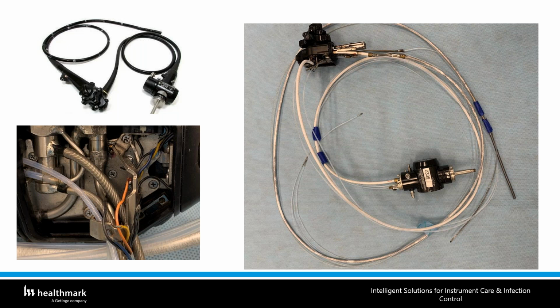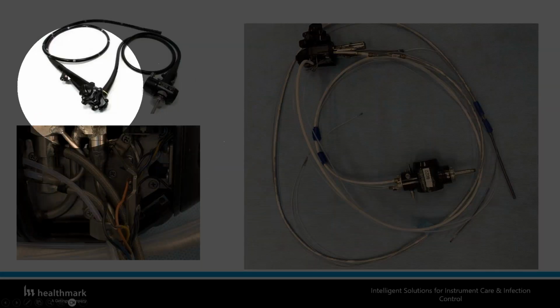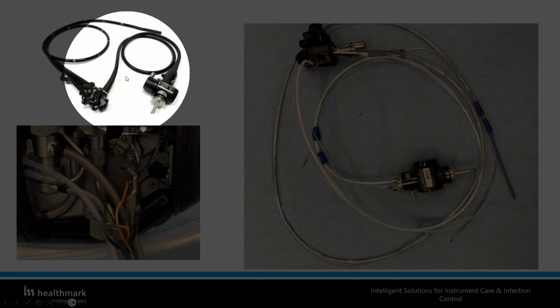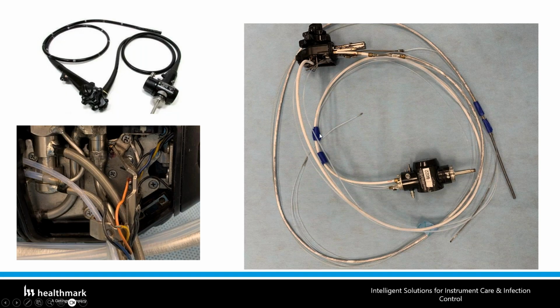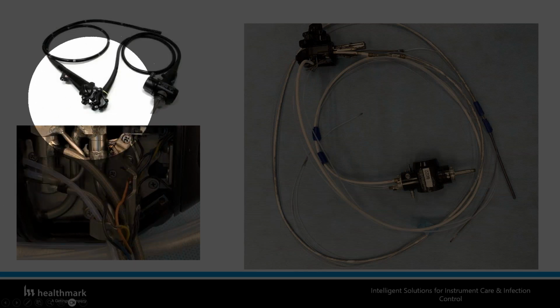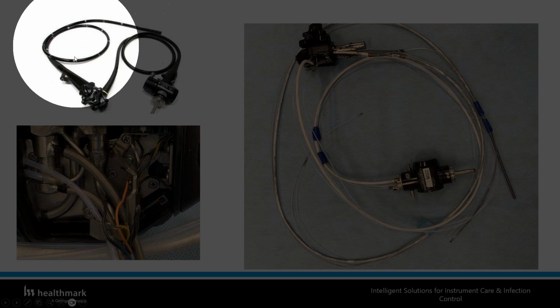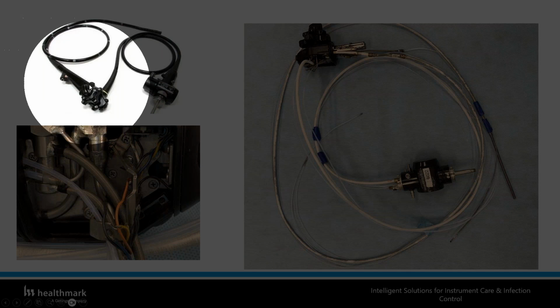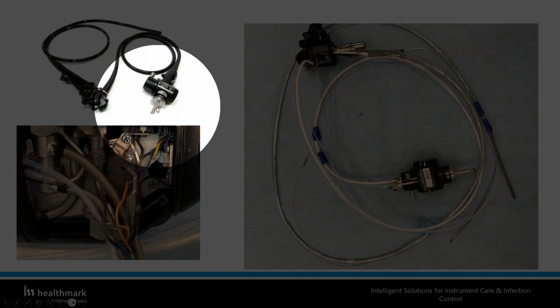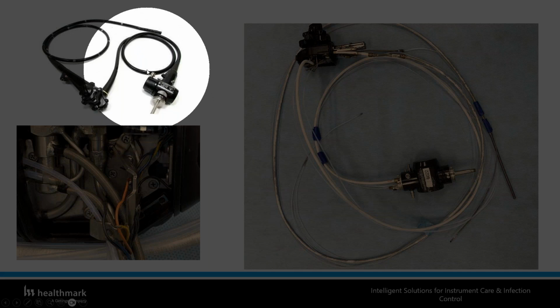For example, one of the things we do as Biomed is look under the hood. So this is a really nice endoscope, and when you take the shield off, this is what you see inside it. Then you take off a little more, for example under the knobs, and you see all these angle wires going out, some going to the patient and some to the machine and umbilical cord. You see that, for example, the fluid comes from here, goes to this area, and then through this 90-degree angle goes back and to the machine. And for example, the suction goes to the wall suction, or if you attach water or air, it comes from this and goes to the patient.